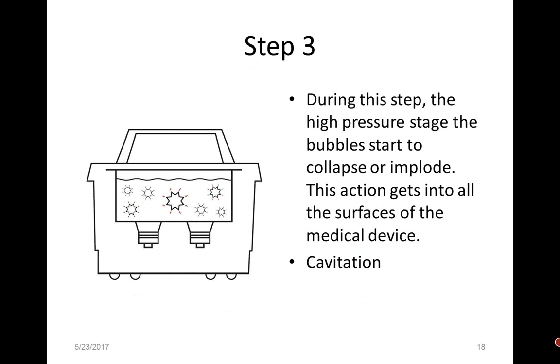So the basics, again, is a process of additional deep cleaning action. So you've usually done some pre-cleaning. The medical devices have specific exposure times to be cleaned properly. So you need to follow the device manufacturer's IFU for the correct exposure time. Following the cleaning, instruments must be thoroughly rinsed. Think of your dishes. When you pull them out of a sink, they have that suspended soil and grease or food on it, and you rinse it off. It is the same thing with the sonic. When you pull it out, if your sonic doesn't have an automatic rinse, you still have to rinse it out before it goes to its next stage.